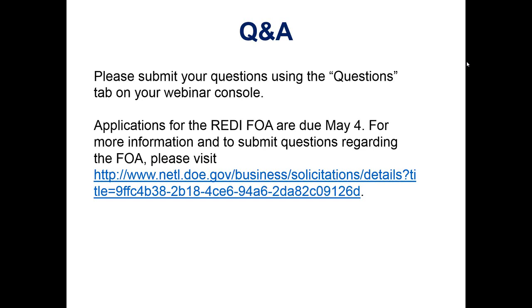Okay. This is actually a follow-up question. The person who asked the previous question about flow batteries wants to confirm: are you saying that they can simultaneously operate as power and energy at the same time, or sequentially? Well, in general, you want to look at what function you can derive the most revenue from, and that will generally mean that you're going to go sequentially. However, some of the functions can be done simultaneously. For example, you could reserve a certain amount of your storage to respond to small fluctuations and do the rest with load shifting.